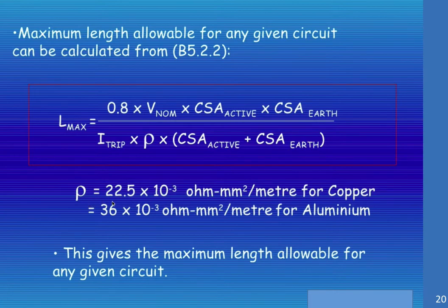The ρ for copper is 22.5 × 10⁻³ ohm-mm²/metre for copper, and if you do happen to be in some unusual situations where we're using aluminium, it's 36 × 10⁻³ for aluminium. This effectively gives you the maximum length allowable for any given circuit.